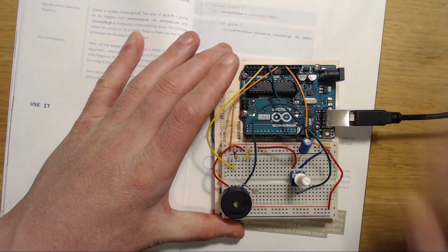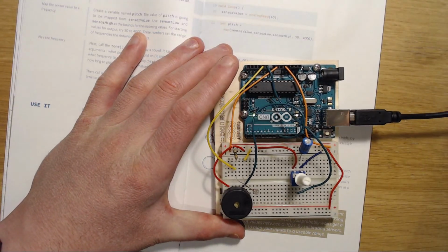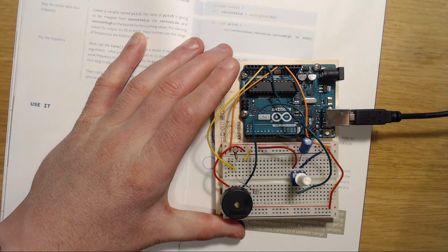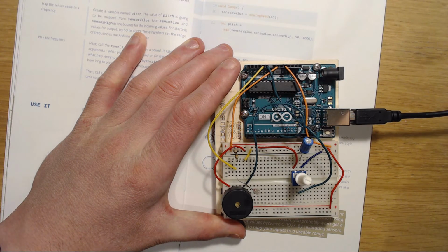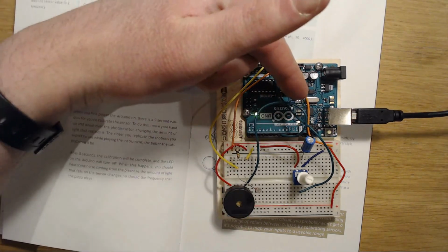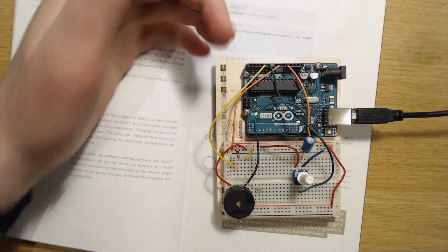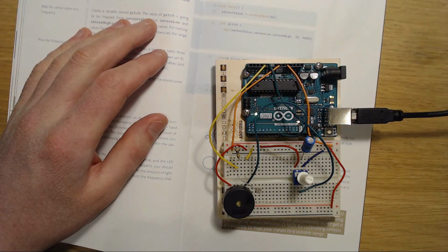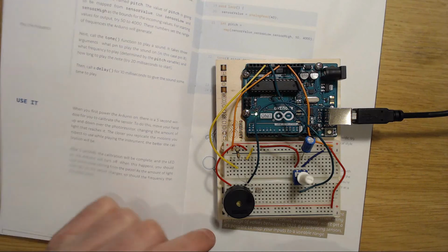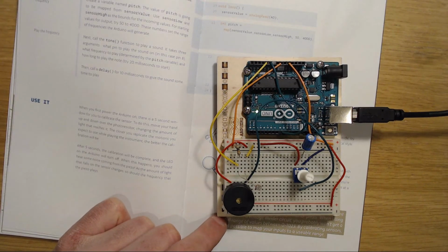So as can be seen, let's see what happens if we just refuse to calibrate it because we're bad people. You can see the light goes on telling us it's being calibrated, but we're not actually covering it, so it's just getting... yeah. Basically, because its lowest value and highest value are so close to each other, even a tiny change can suddenly have radically different results. That's why calibrating is important. You need to know the limits of how it's going in one direction and the other, otherwise it all gets screwy.